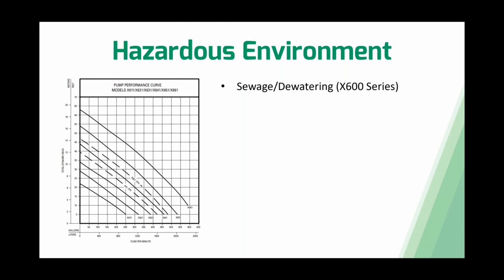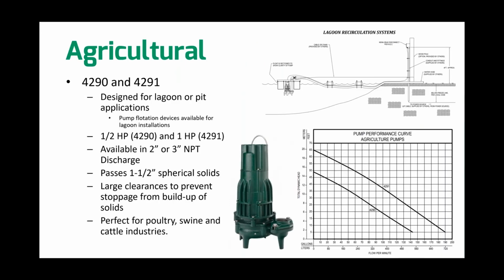Like the 661 can get over 550 gallons per minute at 15 feet of head, and that pump can go over 60 feet of total dynamic head if you're needing low flow options. But what I do want to point out here is the dashed lines that you see in the pump curve. It's a little bit different than what we've seen in some of the products that we've talked about before. These are the single phase pump curves. So the 641, the X641 and the X651 at single phase do a little bit different performance than the 3-phase options. So the next category of pumps we're going to be talking about is the agricultural pumps.